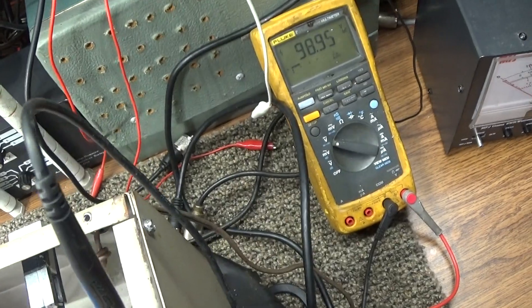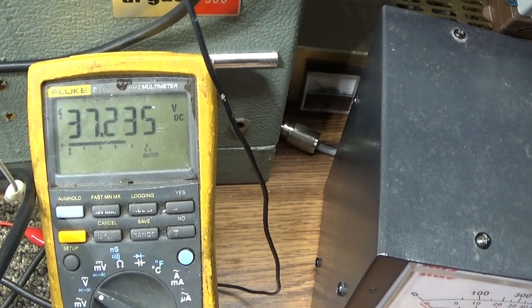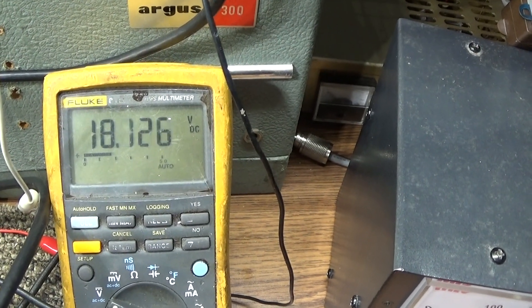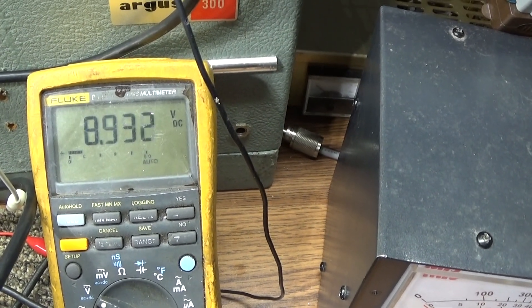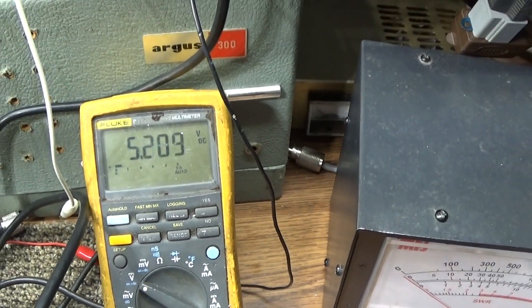And also real quick I'm going to touch my made up 100K to the high voltage too using my screwdriver. Notice I'm way up on it, no metal close to me or close to it. Now I got the screwdriver on there with the 100K resistors and you can see how fast it's draining it down now, pretty quick.